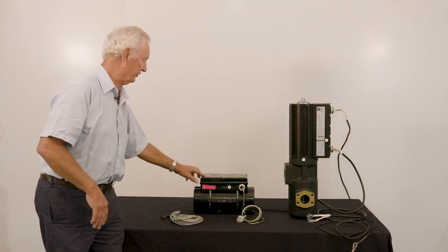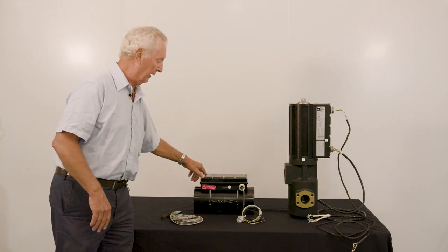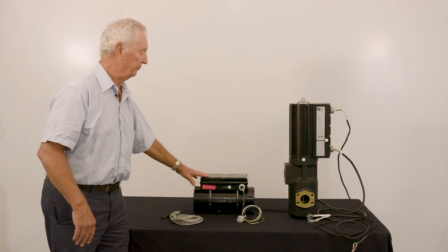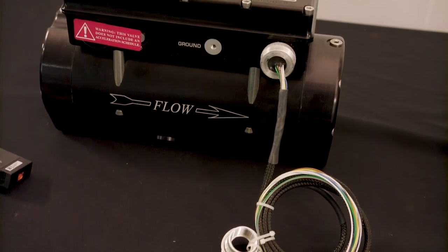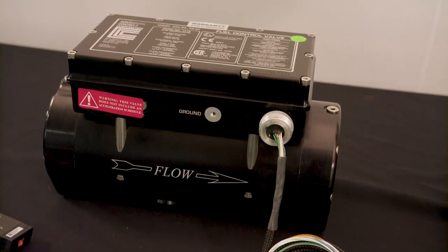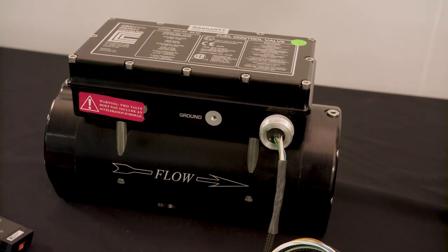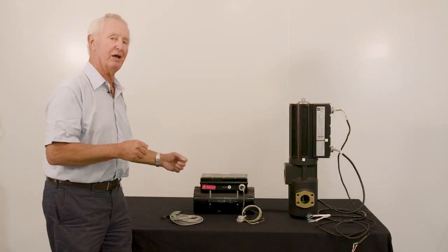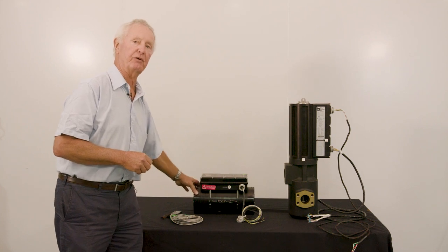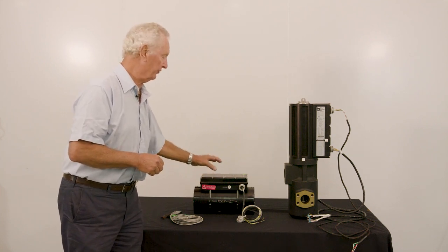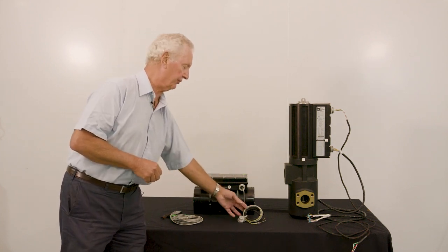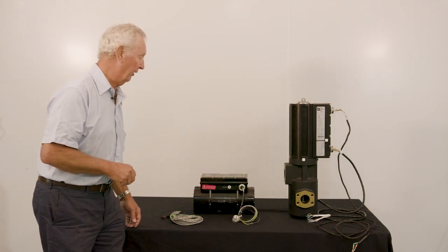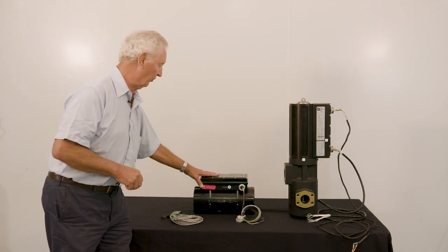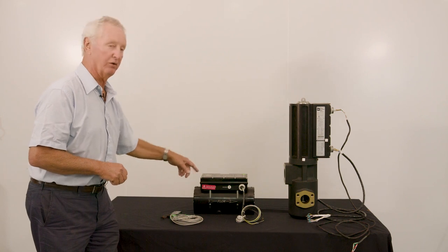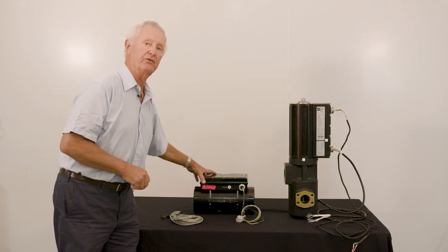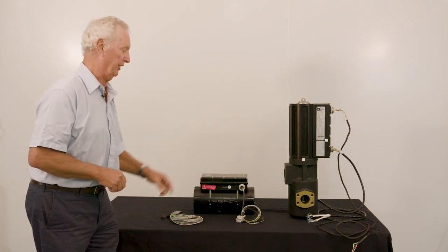Another version, the CCC, Continental Controls, is a similar device except it only needs 24 volts, achieving the power by using the 24 volts to control a pilot. The actual muscle to move this valve is the pressure of the gas itself. So by using the power from the gas, you can reduce the amount of power you need to put in through the cables, making this a more easily handled, and considerably smaller device. In fact, if you went to lift them, you'd see a huge difference—this one is quite liftable, that one's fairly heavy.